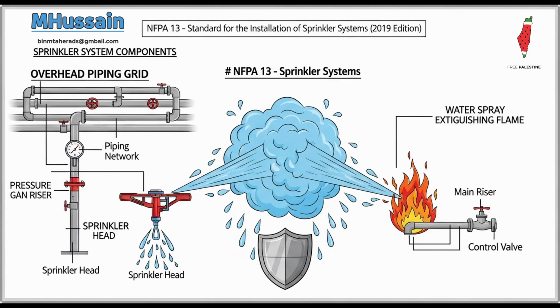The big benefit of using a higher K factor is that you can achieve the necessary flow density, the amount of water per square foot, at a much lower residual pressure. This really eases the demand on the water supply and the pumping system.